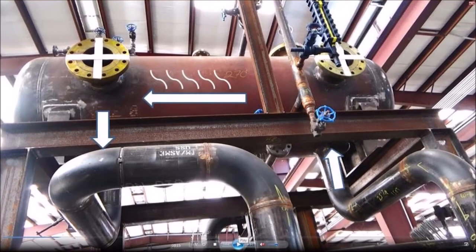This particular hot oil thermally cracks as it decomposes over time. By passing the hot oil and fresh nitrogen through the expansion tank, this will allow the cracked vapors to vent out of the hot oil system. Once the oil is settled, the hot oil can bypass the expansion tank and this will reduce heat loss.